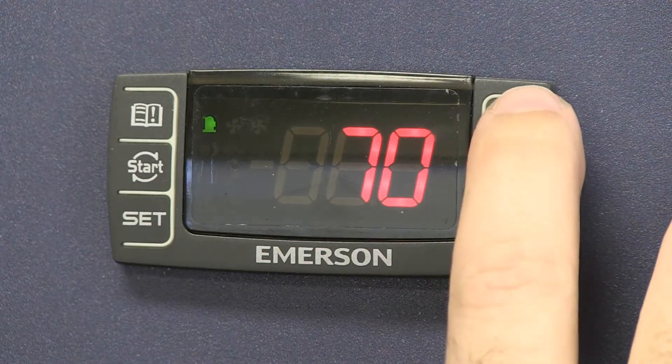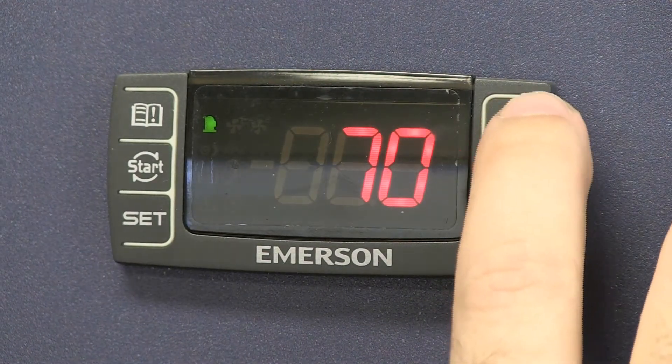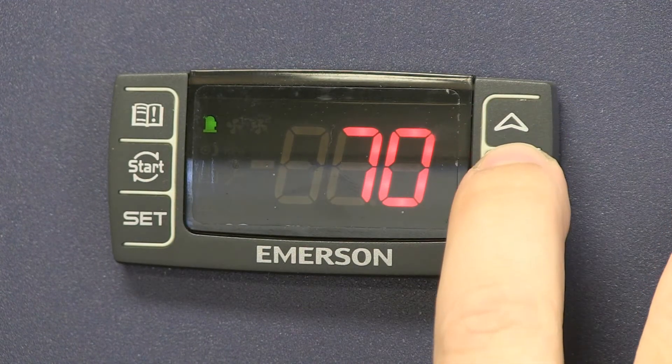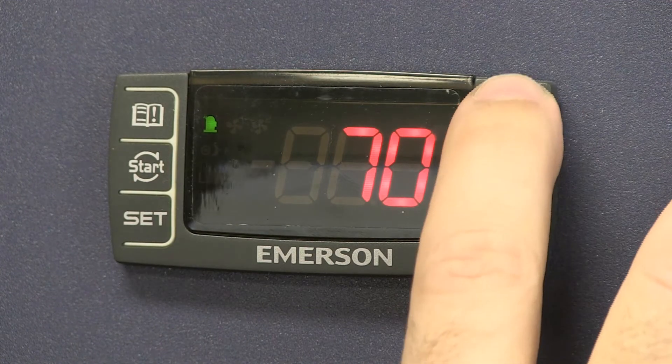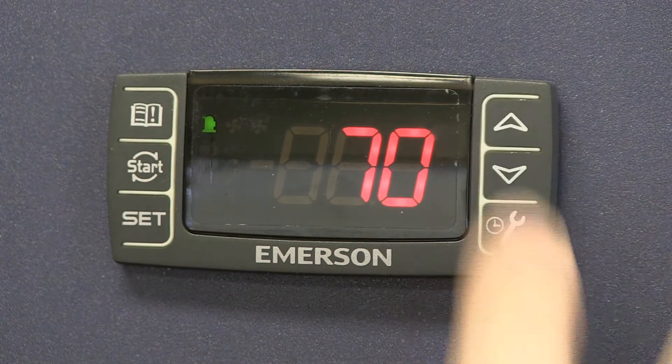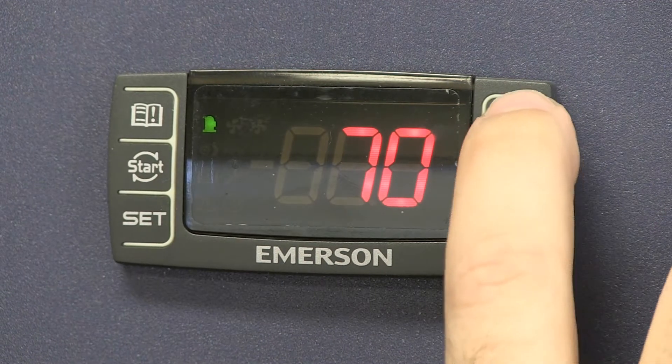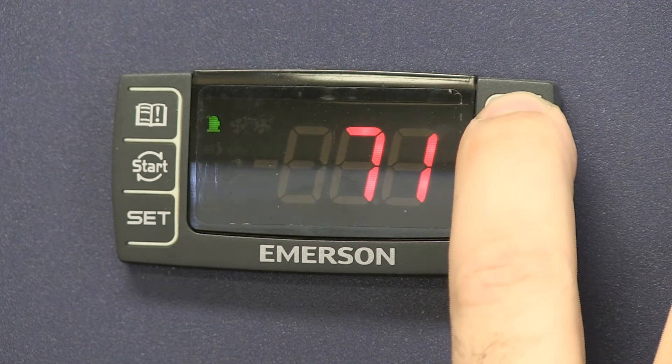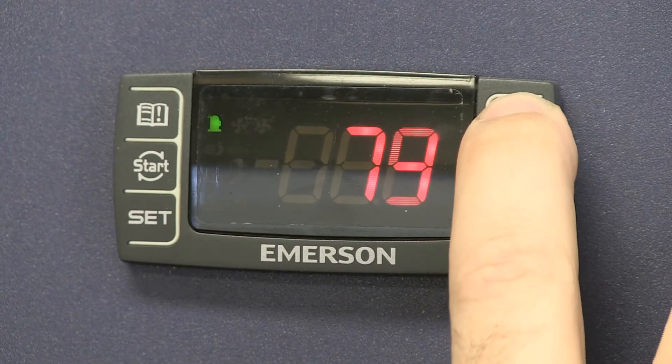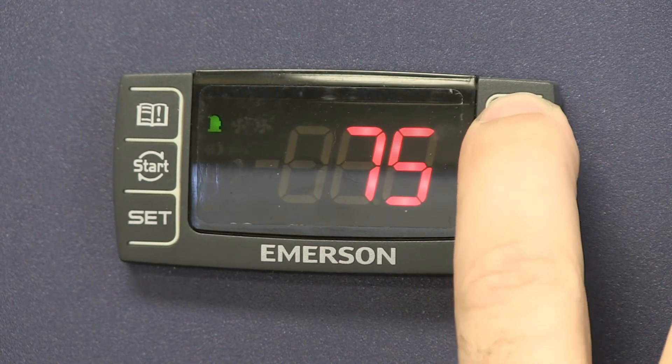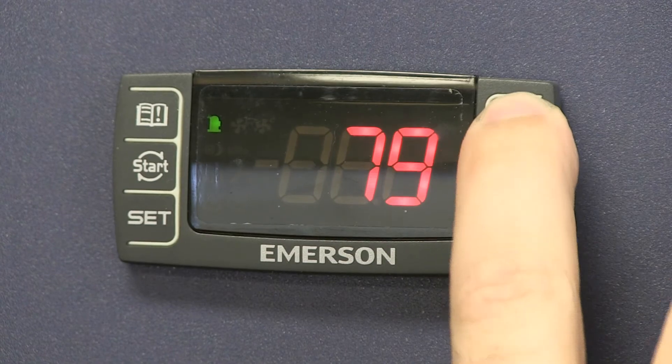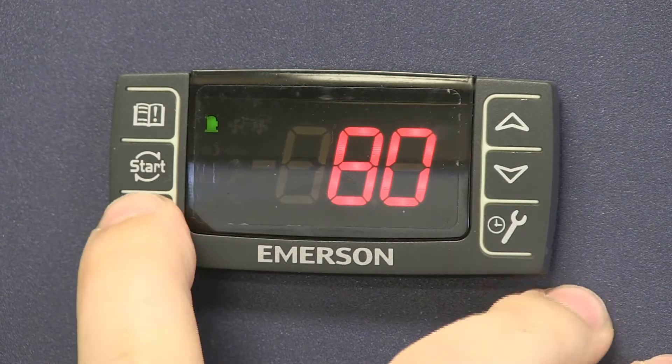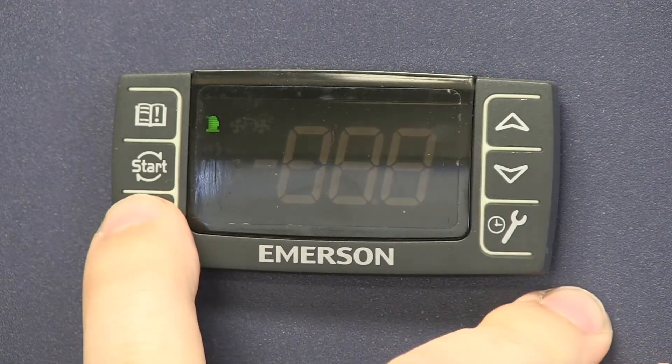This is the cutout temperature. So if we want to raise it, let's say to 80 degrees, this will maintain a higher condensing temperature. Hit set.